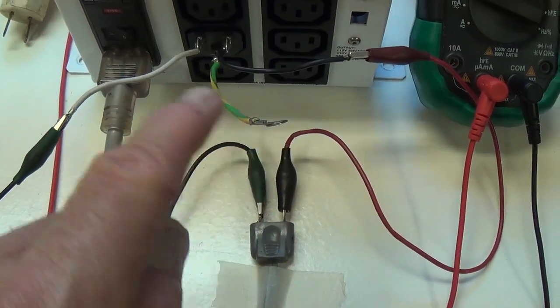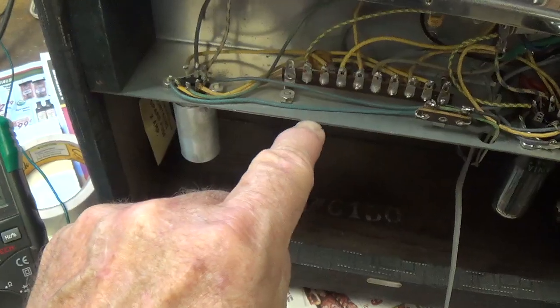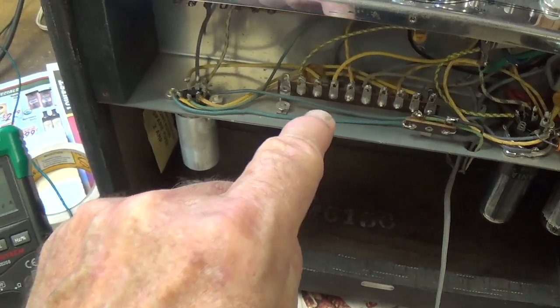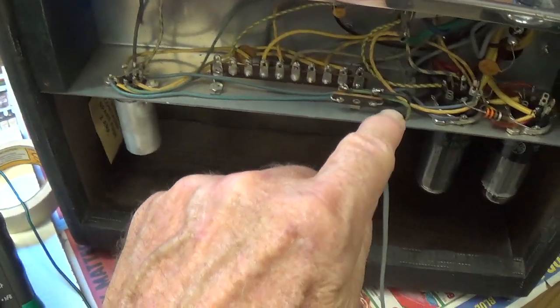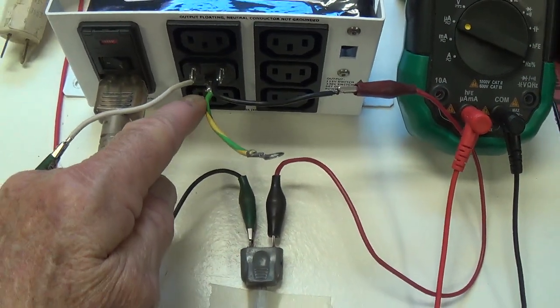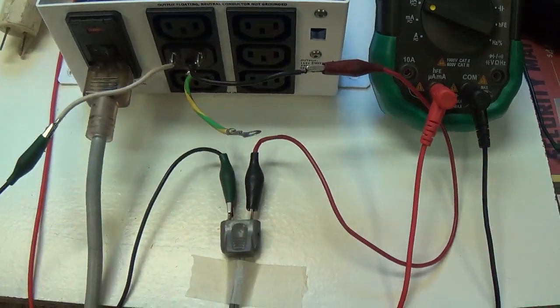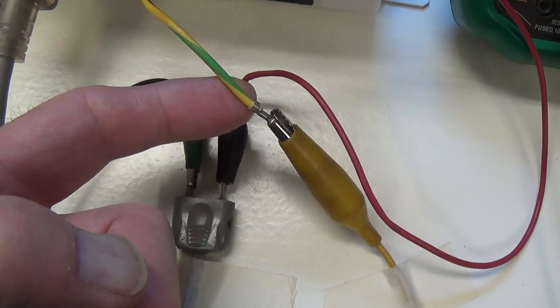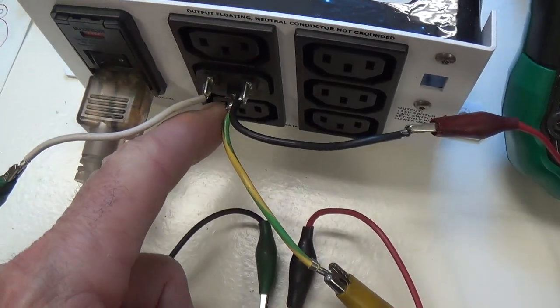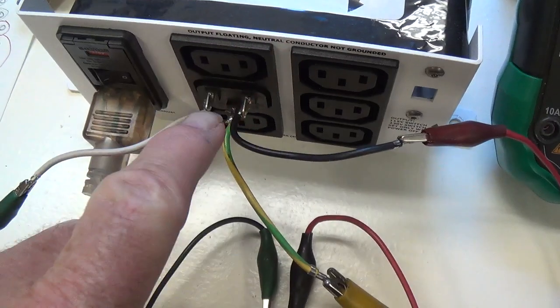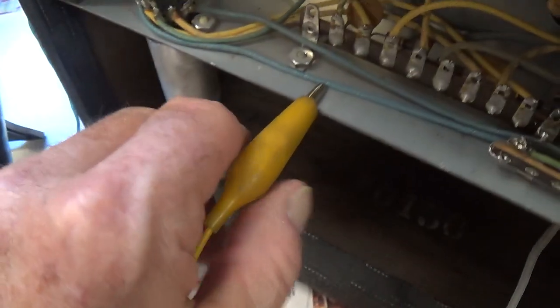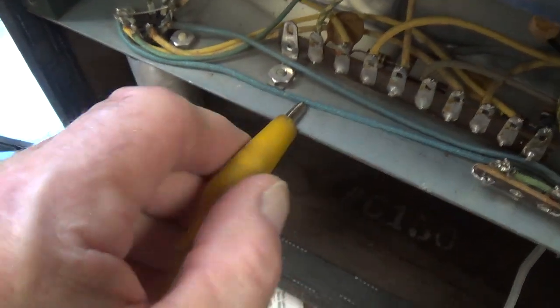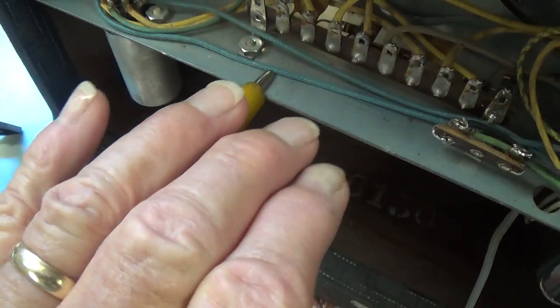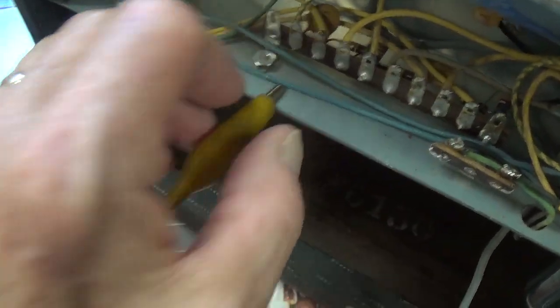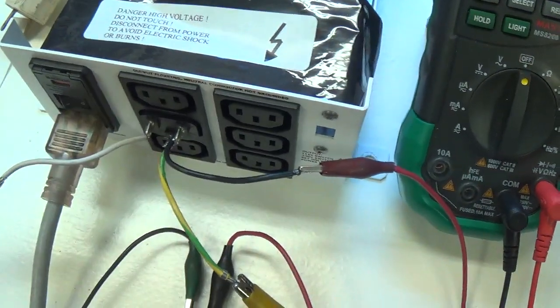Okay, if we jumper from here to the chassis of the amplifier circuit, which is exactly what would happen if you had a three-wire plug, right? Isn't the green wire bolted to the chassis? It would come over here and plug in right down here, and it would connect to that point. So let's do it and see how it changes things. Okay, here we go. I've installed a jumper between the grounding lug of the isolation transformer receptacle and the chassis of the amplifier. Now this is exactly the same as if we now had a three-wire chassis grounding power cord being plugged in to that receptacle.